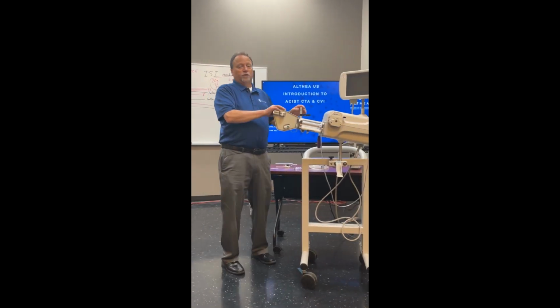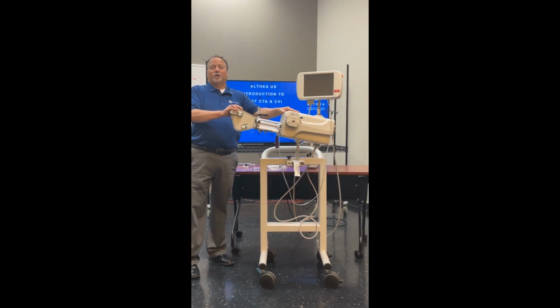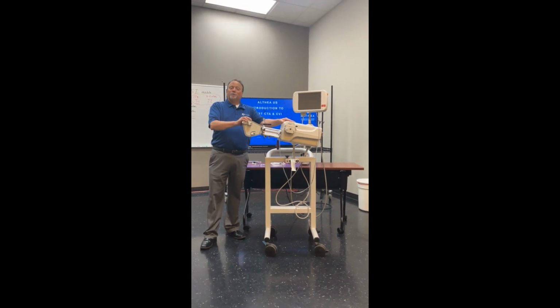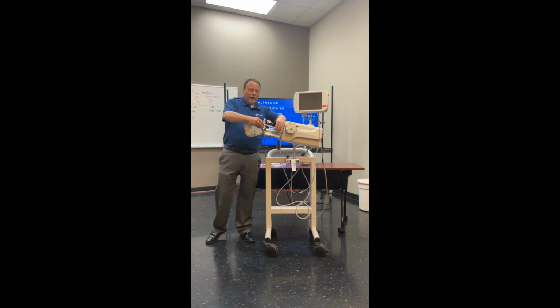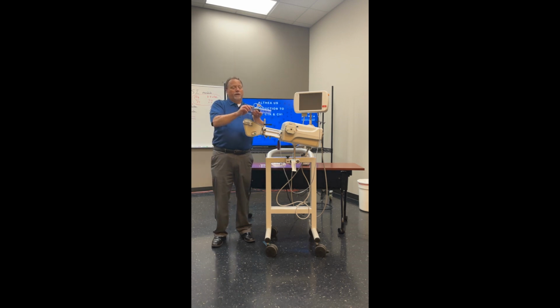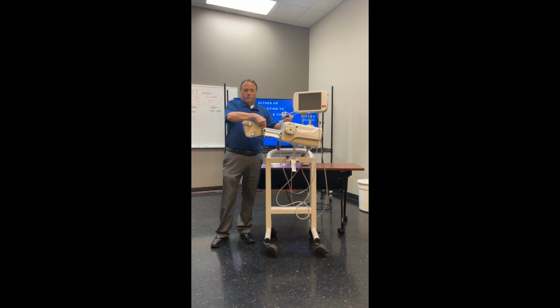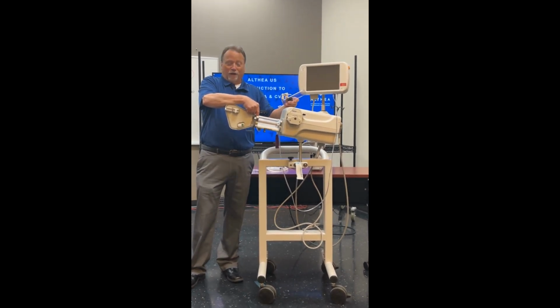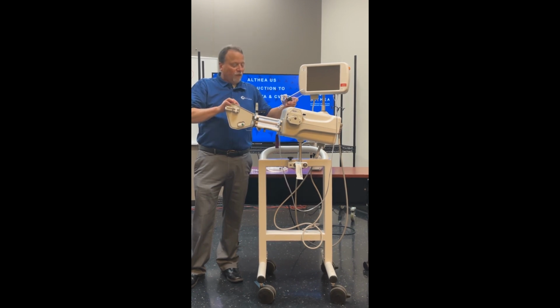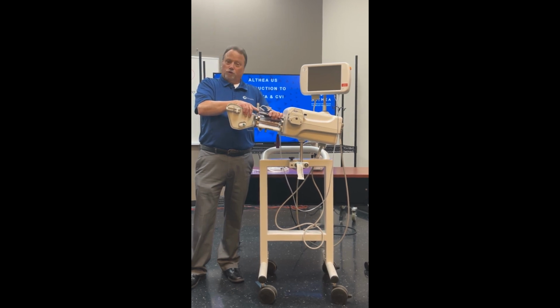Like I said, it's used in angio-interventional, and this is kind of a unique injector for the fact that it's not positioned up and down. It's positioned at an angle. The reason it's positioned at an angle is that when it purges, using the syringe at that angle, the air is pushed out back into the contrast reservoir. It automatically refills, and then it purges, and they have a small bearing in here that will go into the syringe sensor that identifies whether it's purged and all the air is removed or not. So it doesn't have to go up and down, just at an angle, because we all know air goes to the highest point, and at this angle the syringe sits in, it goes to the highest point.